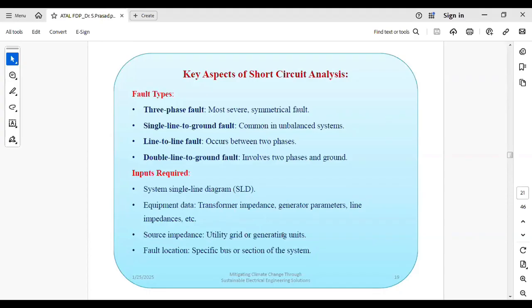That means whenever the PV plant is connected to the grid, the X by R ratio or MVA rating has to be provided by the utilities. Then only can you conduct the short circuit study. Otherwise, you cannot know what short circuiting current will be contributed by the grid. So that information has to be provided by the utilities.